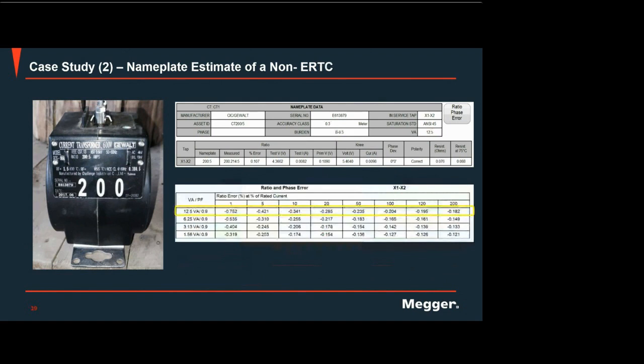So, looking at the rated current to check, maybe it is an ERCT, who knows? Looking at the error at different rated currents, as you can see here, it fails on 1%, of course. It is not 0.3 on 1%. It is not 0.3 also on 5% of rated current, but it is 0.3 from 10% up to 100% or 200% of the rated current. So meaning to say, this is just a standard CT. The accuracy starts from 10% to 100%, 150% of the rated current. So it is a non-ERCT.